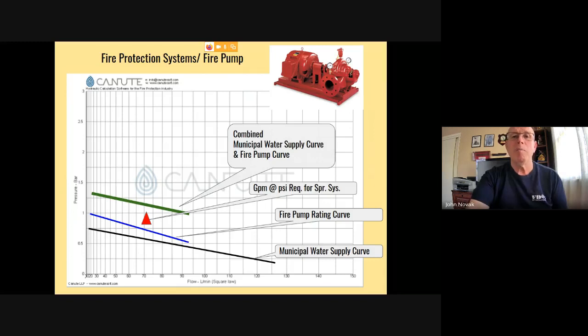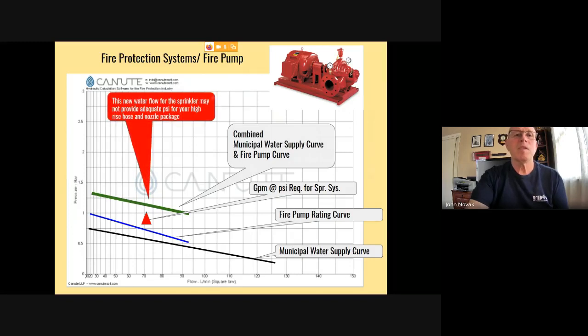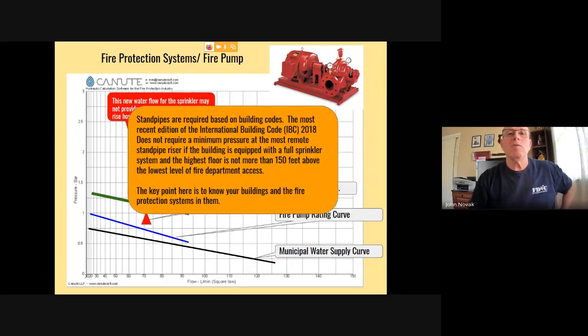So just because you have a fire pump in a building doesn't necessarily mean it's going to meet the needs of your standpipe system and your high-rise pack that you carry. So the water flow for the sprinkler may not provide adequate PSI for your high-rise pack and your nozzles. We'll show a couple illustrations coming up real shortly. So just a little note on standpipes. Standpipes are required based on building codes. The most recent edition of the International Building Code does not require a minimum pressure at the most remote standpipe riser if the building is equipped with a full sprinkler system and the highest floor is not more than 150 feet above the lowest level of fire department access. So the key here is to know your buildings and the fire protection systems that are in them.